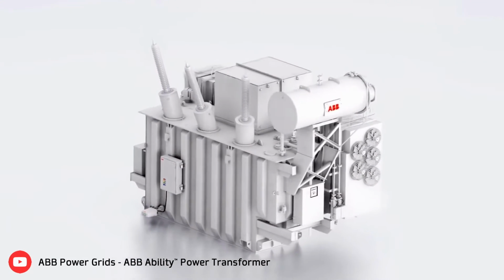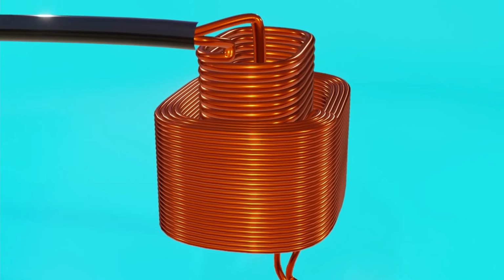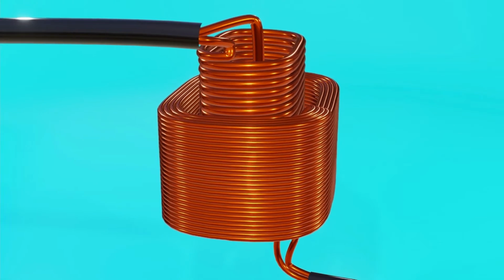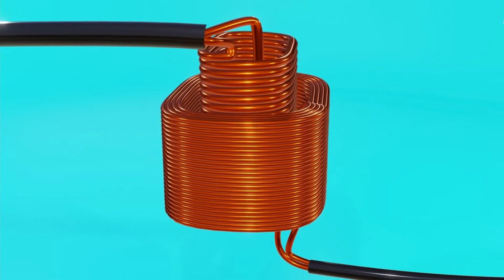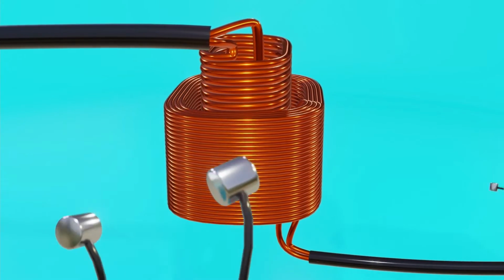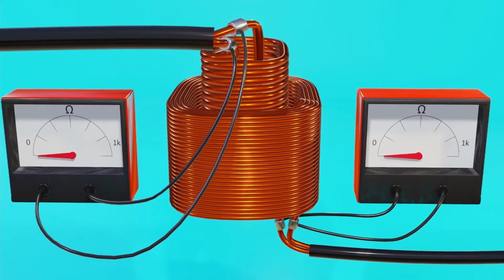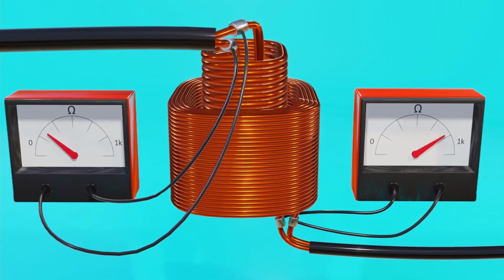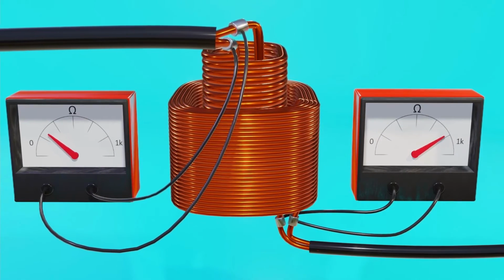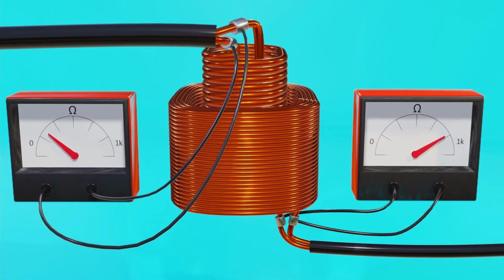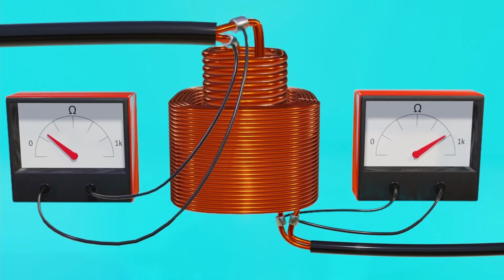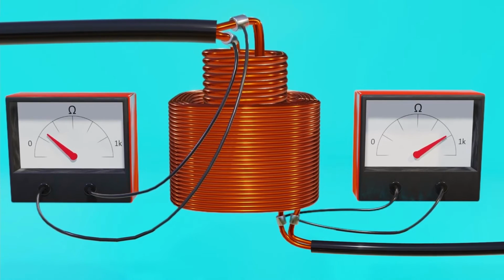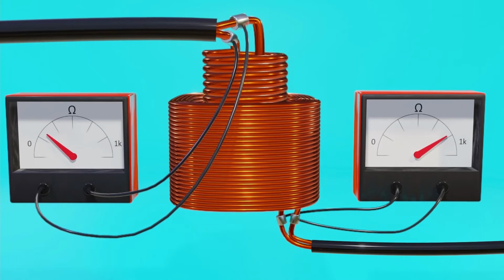so there's no point in making the wires bigger than necessary. This same difference in diameters means that in case we have a transformer in which we do not know which terminal corresponds to which coil, since they are generally covered, we could measure both resistances and deduce that the one that is smaller corresponds to the coil with the fewest turns, since, as we saw in the chapter on resistors, a greater cross-sectional area and a smaller length means less resistance.